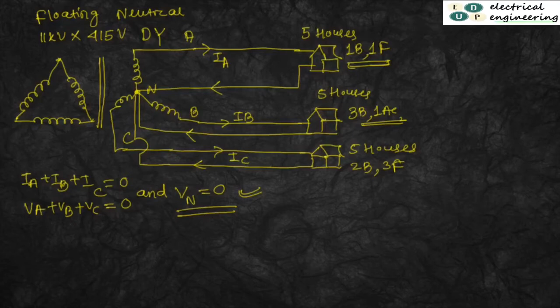But actually what happens? Suppose in phase A the working load is one bulb and one fan in the houses, operating. In the second phase, B phase, 3 bulbs and let's say 1 AC. And in the third phase, C phase, let's say 2 bulbs and 3 fans are operating. So from the user's point of view, the loads are unequal. Because of this, a voltage appears at VN. That means VN is not equal to 0, IA plus IB plus IC is not equal to 0, and VA plus VB plus VC is not equal to 0. So some voltage will appear across the point N. This is called floating neutral.